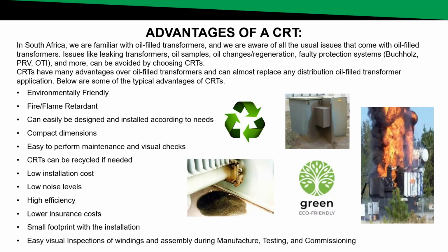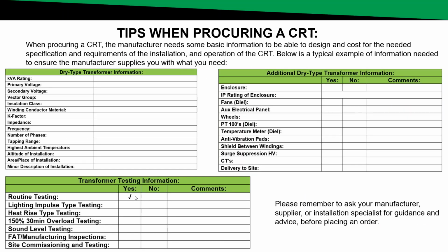And then, of course, what type of testing would you like to be done on your cast resin transformer? Obviously, routine testing has to be done by the manufacturer, and then obviously all the other types of tests that are required. Please just keep in mind, should you require some of these type tests, they are very costly to conduct. Sometimes if you need a full type test to be done, the actual cost of the type test becomes more than the actual transformer.